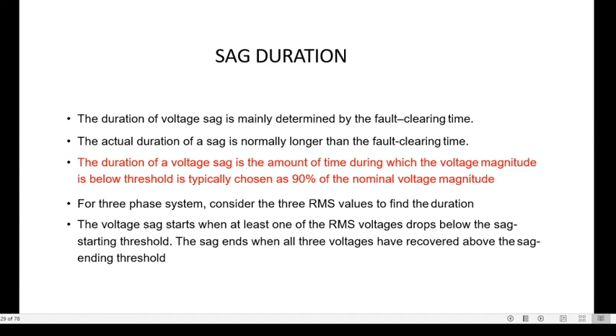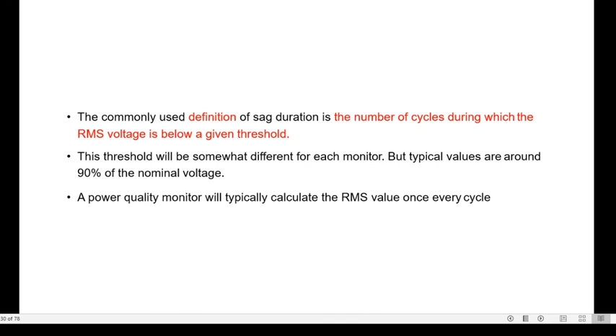The commonly used definition of the sag duration is the number of cycles during which the RMS voltage is below a given threshold. As I told you, instantaneous is 0.5 to 30 cycles, momentary 30 cycles to 3 seconds, and temporary between 3 seconds and 1 minute. These thresholds will be somewhat different for each monitor, but typical values are around 90% of the nominal voltage. A power quality monitor will typically calculate the RMS value once every cycle.